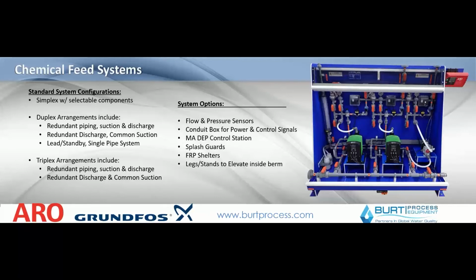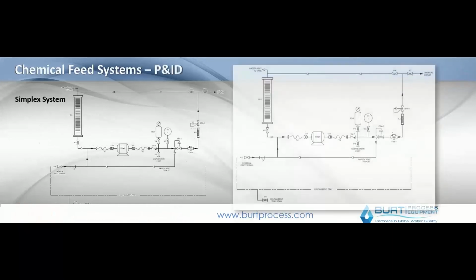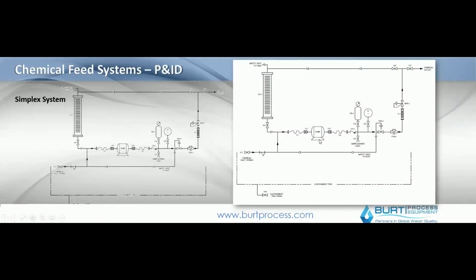Majority of chemical feed systems are built in either a simplex design, a duplex design with duplex lead lag or duplex redundancy, or as part of a triplex arrangement. And obviously, we've gone through many before, a lot of the different system options. From a P&ID perspective, you have the metering pump here. This is obviously for a simplex design. This is what I said about the check valve, the Y strainer, which comes up into the pump. You have your calibration column, pulsation dampener, pressure relief, and then back pressure valves. Back pressure valves are somewhat common on a lot of metering pump applications, because you want to get more of that consistency in the pump. So you want to put some artificial back pressure in there as well. Depending on the flow that's involved in the system, you can also see things like flow meters in the system. That's very true when we have very high flow applications going on as well.